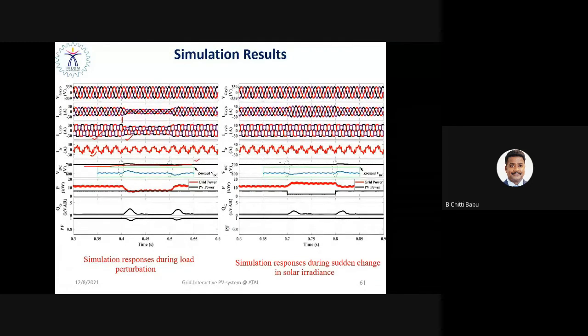When a sudden change in irradiance happens, from 1 kilowatt per meter square to 300 watts per meter square, the PV power reduces and the grid power increases. Still, during that condition, as the grid power demand is increasing, it also needs reactive power support to maintain the DC link voltage constant. That is, during DC link voltage control, the grid needs reactive power support. But when the power balance is maintained, the DC link voltage is constant, the grid doesn't need any reactive power support, and the power factor can also become unity.